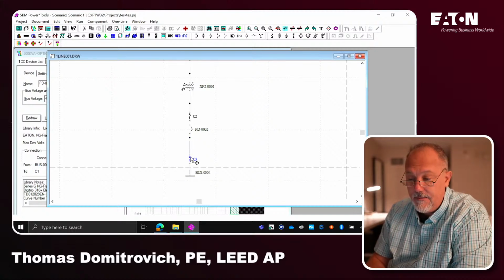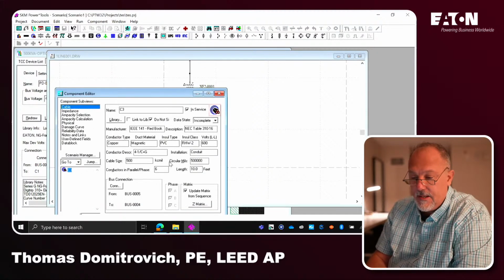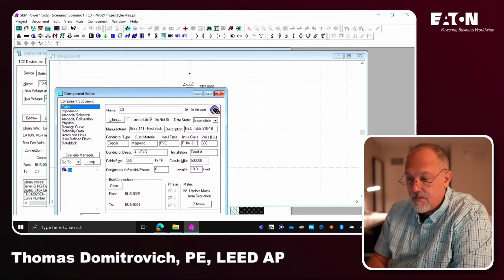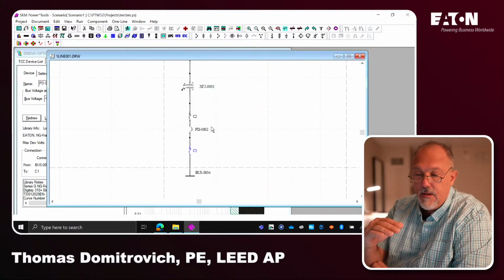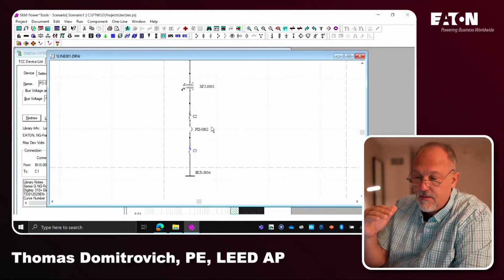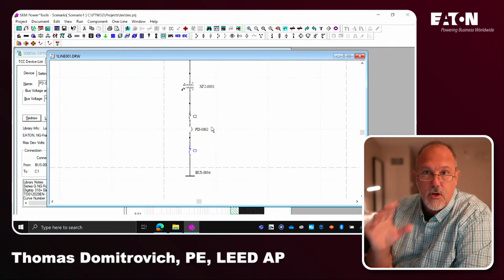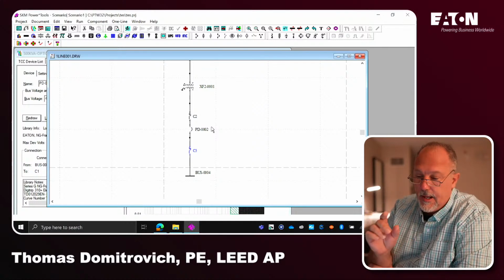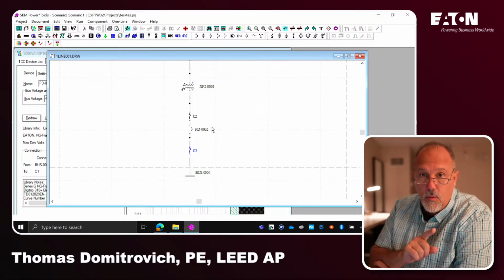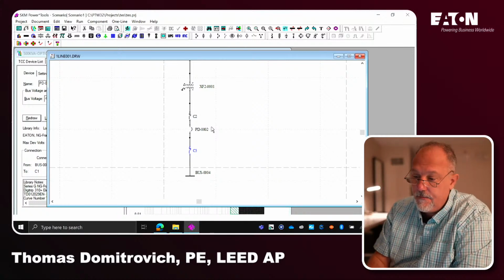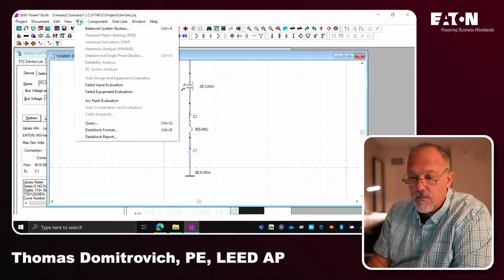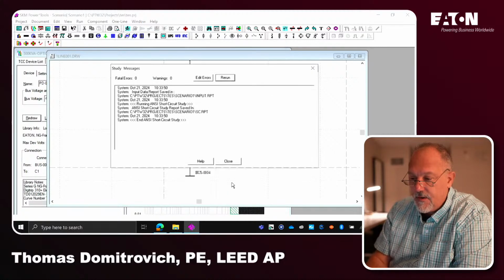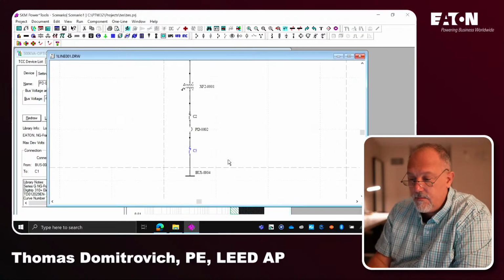So now what I've done is bus 5, there's my 10 foot. So now bus 5, basically we popped that circuit breaker on the secondary into its own enclosure. And now the incident energy at bus 4 is going to be determined by the clearing time of the secondary overcurrent device, not the primary overcurrent device. And I'm hoping this runs, so let me run. I'm going to run the fault current study first. No warnings, no nothing there.